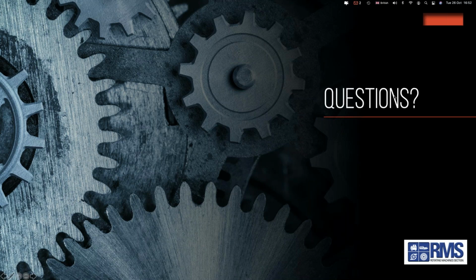So Rob, while the audience is trying to put the questions together, my question is on cyclic and mechanical stress on these 6.6 motors. How much of failure does that contribute to the overall condition of the generator, especially now? Because in the past we used to have the luxury of running the machines for a long period of time, but now, because of certain things that we experience even in the Eskom, you have to run the machines at a certain period of the day, then shut them off and run them again. So how much of a cyclic effect does the environment have on the 6.6 machines?